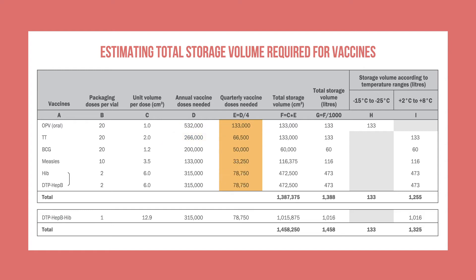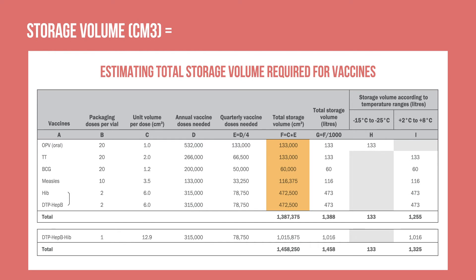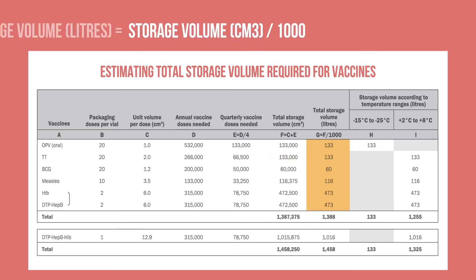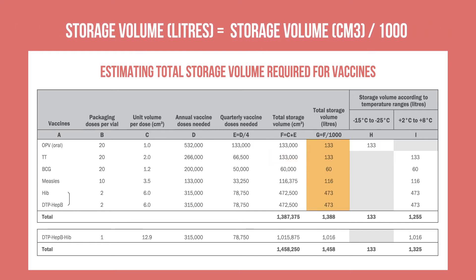Since you are calculating storage requirements for each quarter, divide the annual number by 4 to determine the expected quarterly doses. Here, 66,500 doses of TT are expected. Now calculate the total storage volume of each vaccine by multiplying the unit packed volume by the expected quarterly vaccine doses. The storage volume for TT each quarter would be 133,000 cubic centimeters. Divide by 1000 to convert from cubic centimeters to liters, so TT vaccine would require 133 liters.